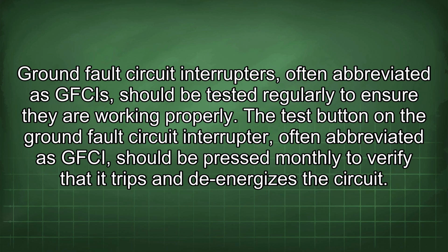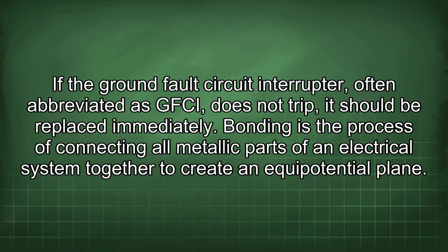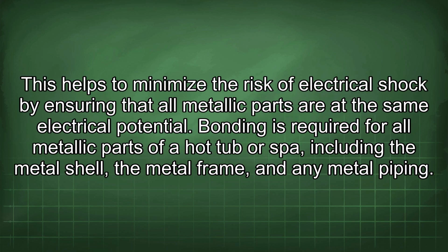GFCIs should be tested regularly to ensure they are working properly. The test button on the GFCI should be pressed monthly to verify that it trips and de-energizes the circuit. If the GFCI does not trip, it should be replaced immediately. Bonding is the process of connecting all metallic parts of an electrical system together to create an equipotential plane. This helps to minimize the risk of electrical shock by ensuring that all metallic parts are at the same electrical potential.